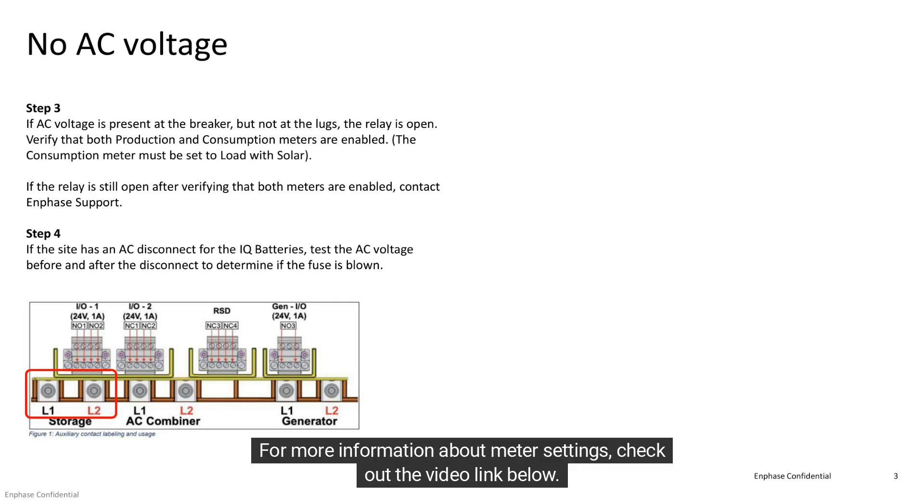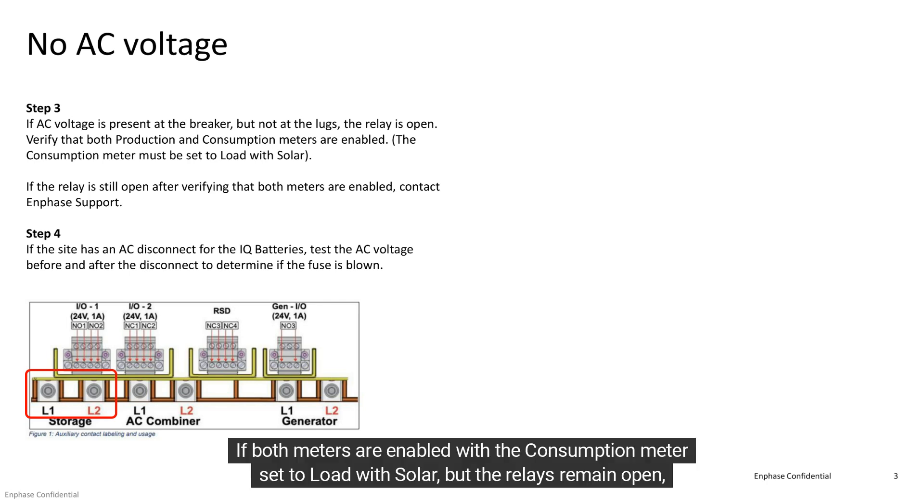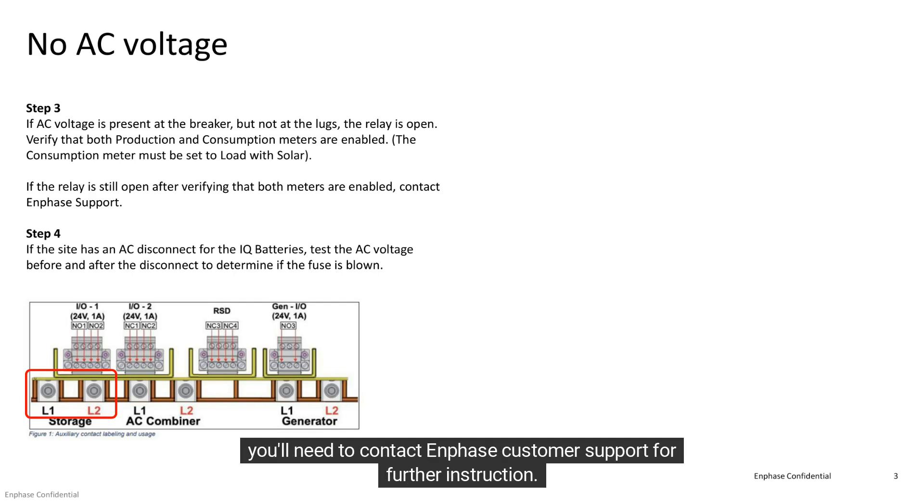For more information about meter settings, check out the video link below. If both meters are enabled with the consumption meter set to load with solar, but the relays remain open, you'll need to contact Enphase customer support for further instruction.